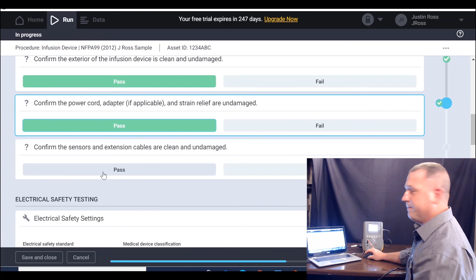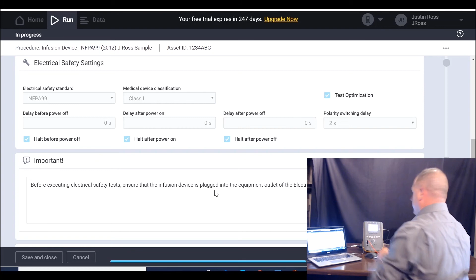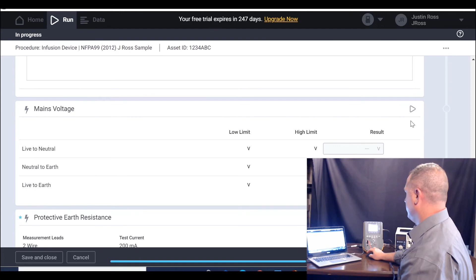Now we're going to start our electrical safety portion. Before executing electrical safety tests, ensure the infusion device is plugged into the equipment outlet of the electrical safety analyzer. Alright, we're going to push play. There's our leakage testing.